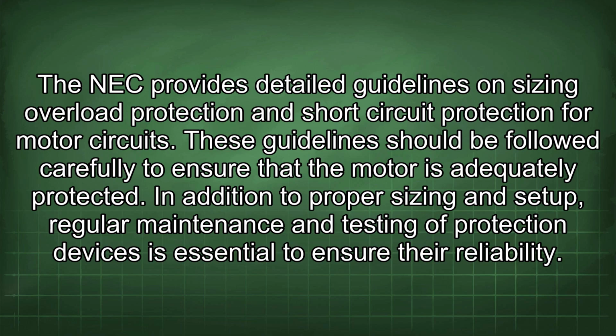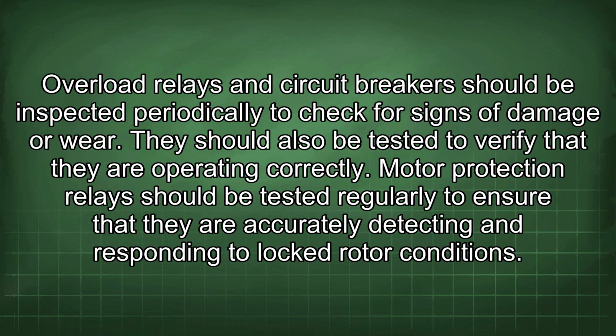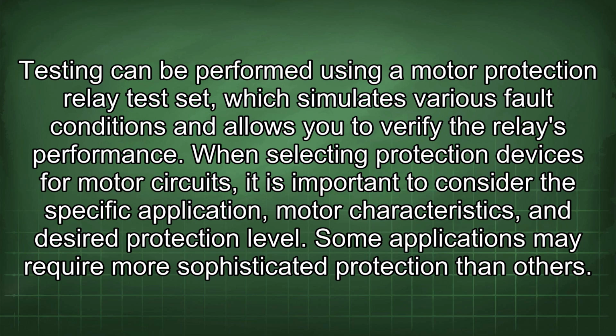In addition to proper sizing and setup, regular maintenance and testing of protection devices is essential to ensure their reliability. Overload relays and circuit breakers should be inspected periodically to check for signs of damage or wear. They should also be tested to verify that they are operating correctly. Motor protection relays should be tested regularly to ensure that they are accurately detecting and responding to locked rotor conditions.